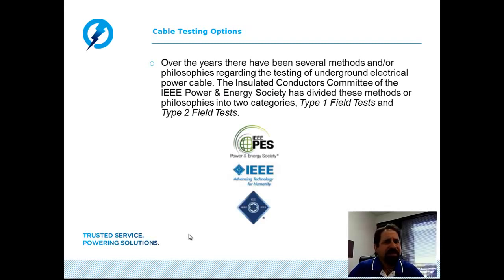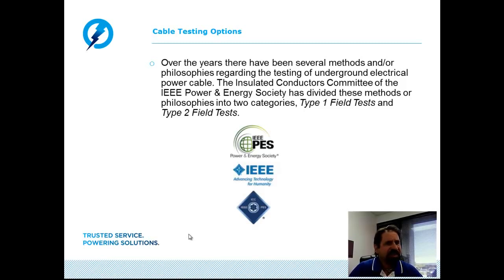Over the years, there have been several methods and philosophies regarding the testing of underground electric power cables in the field. The Insulated Conductor Committee of the IEEE Power and Energy Society has divided these into two fundamental categories: the Type 1 field test and the Type 2 field test. A Type 1 test is intended to detect defects in the insulation of the cable system to improve service reliability after the defective part is removed and appropriate repairs are performed. These tests are usually achieved by application of moderately increased voltage across the insulation for a prescribed duration, and are categorized as pass or fail.